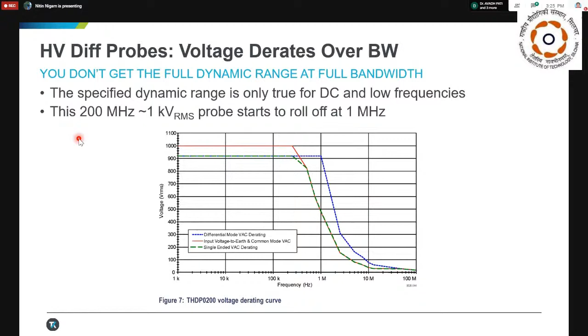Now let's say I use the same probe with a gallium nitride based device which is rated to work at 600 volt and, let's say, 100 megahertz. I know that at 100 megahertz the probe is not rated to work at 600 volt, so it drops down drastically. You cannot characterize the actual characteristics of the switch with this probe, and this happens with all probes. This example shows the roll-off graph of a differential probe at 1 megahertz. You don't get the full dynamic range at full bandwidth. This is one key critical difference that needs to be understood when measuring any gallium nitride or silicon carbide based devices.